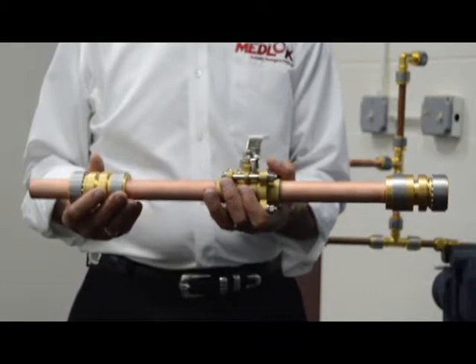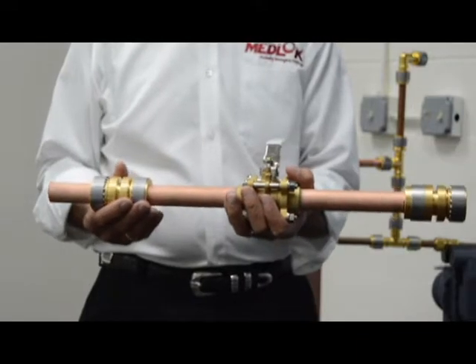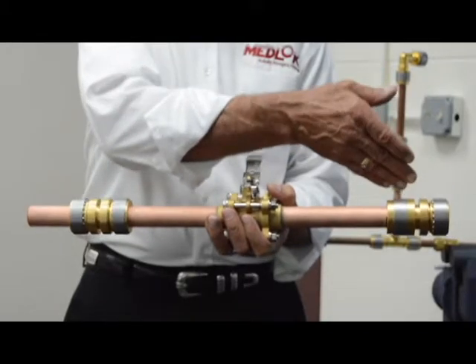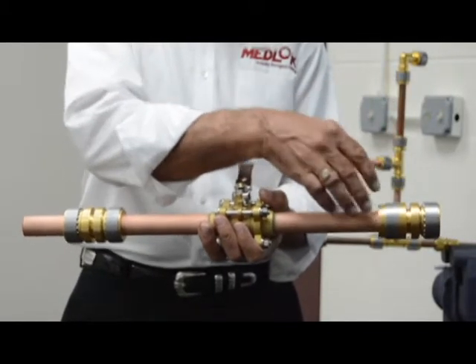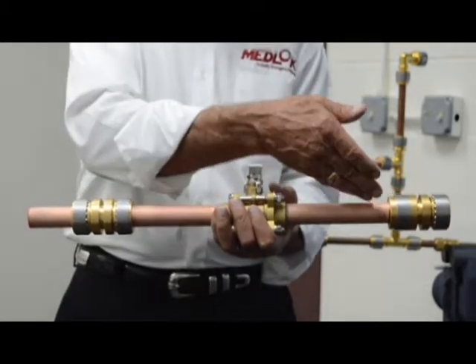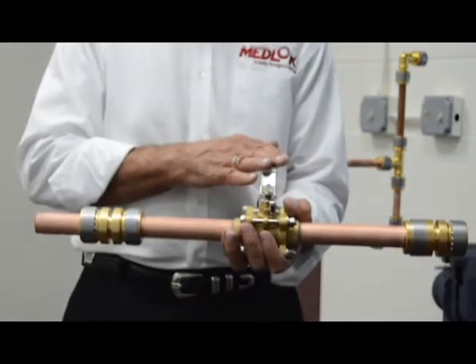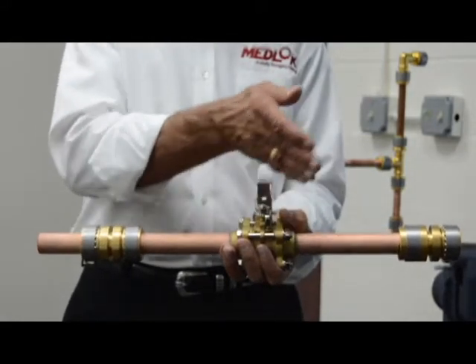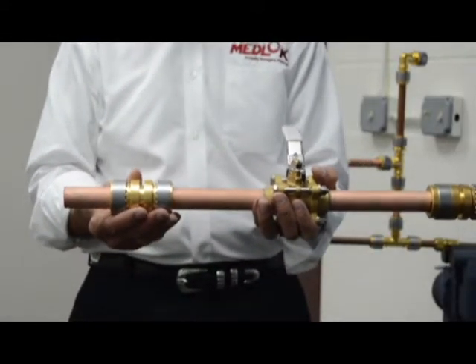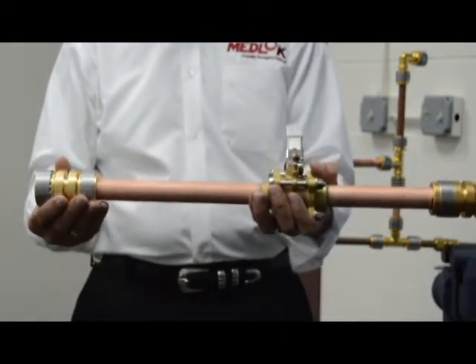One excellent application for the Medlok fitting is to tie into an existing line in a hospital where you need to make modifications downstream. Simply turn off the gas in the line, cut into the line, and install the fitting. We've previously installed this fitting here — you can see the depth insertion mark — and tested the fitting. By installing it and making a quick swage into the existing line, you can shut off the valve, isolating the system. This can then be turned back on, and you're free to move downstream to make your modifications. The slip coupling is available to easily tie in to the other line.